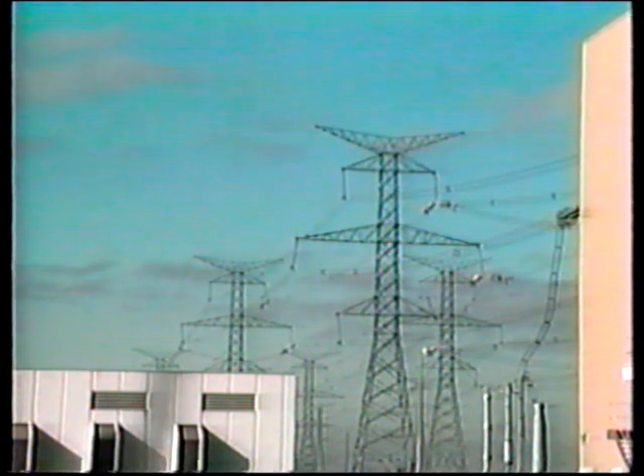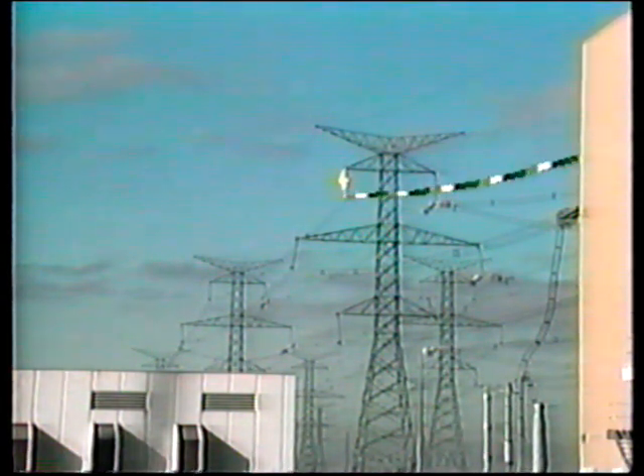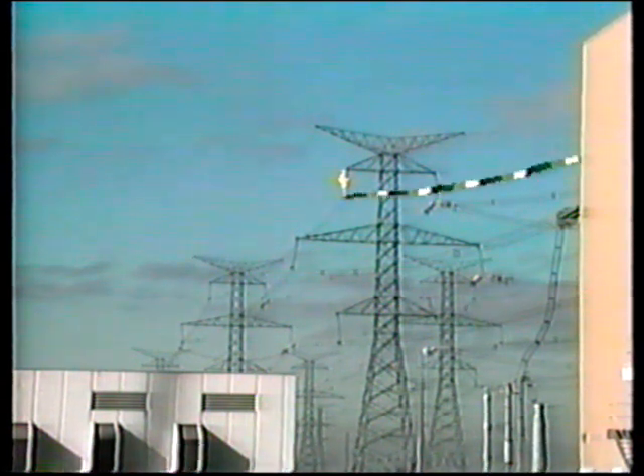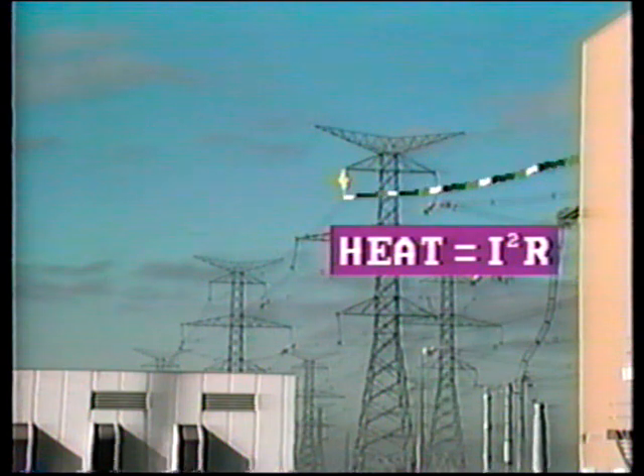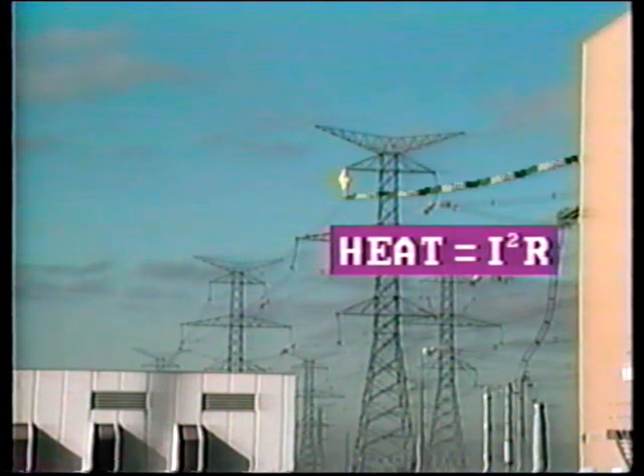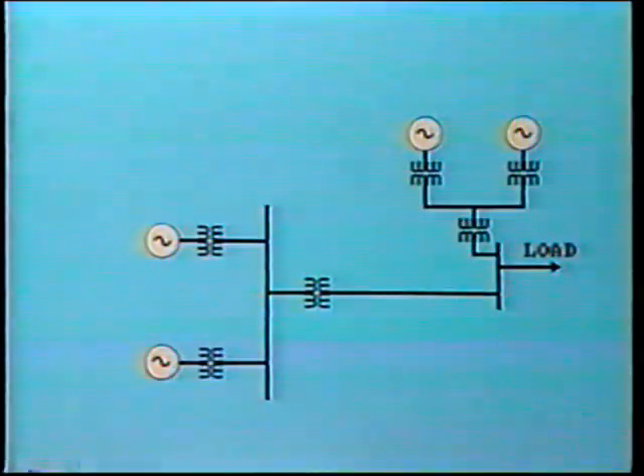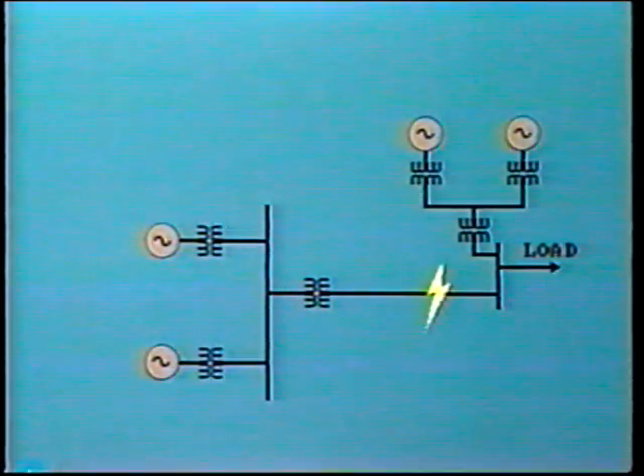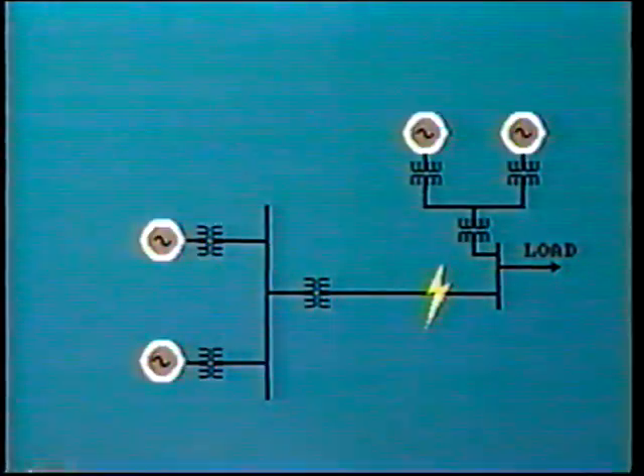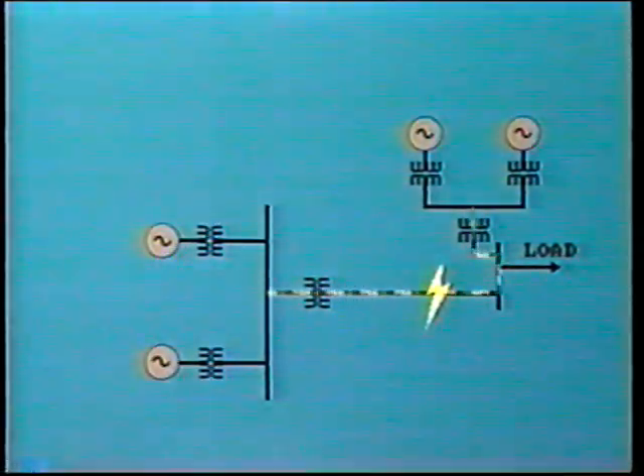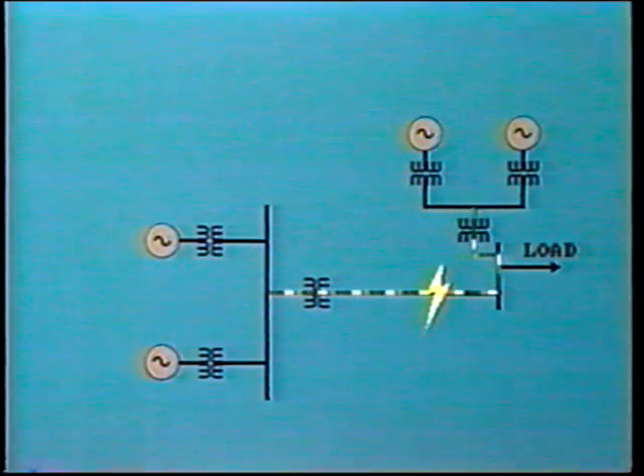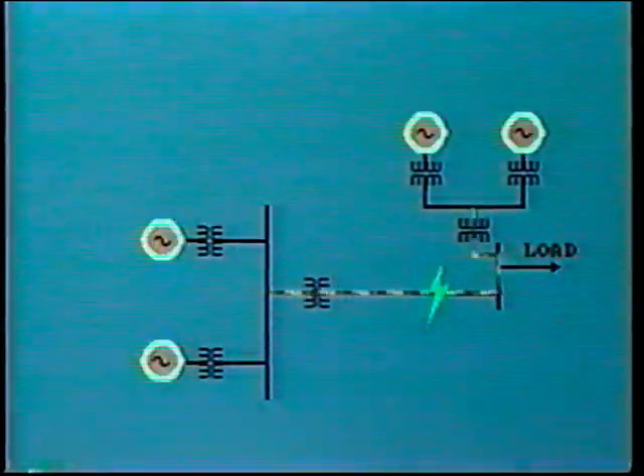All of these abnormal conditions will result in a fault. That is, an unwanted short-circuit connection between one phase wire and another, or between a phase wire and ground. The consequence of the fault is usually a dramatic increase in the value of current flowing, and the resultant increase in heat produced in the conductors is the main cause of damage. The actual magnitude of fault current depends upon the amount of power available to feed into the fault. It's also dependent upon the resistance to flow, that is, the impedance between the fault and the source of power supply.